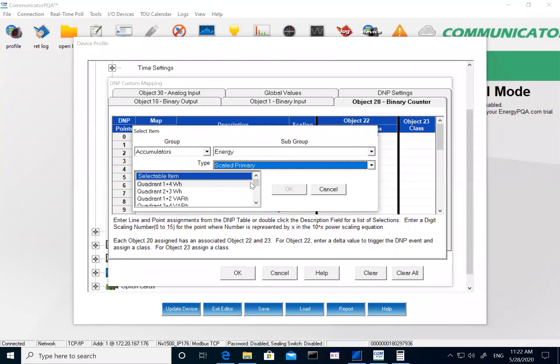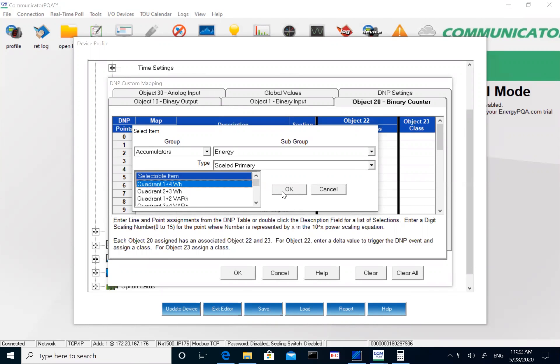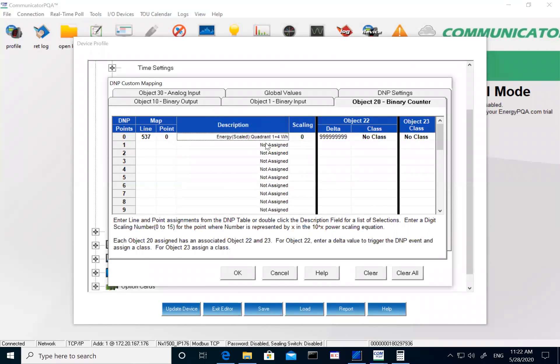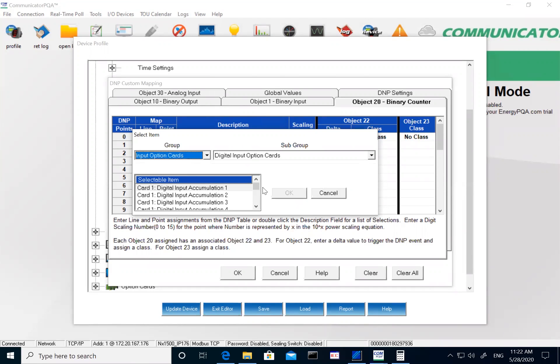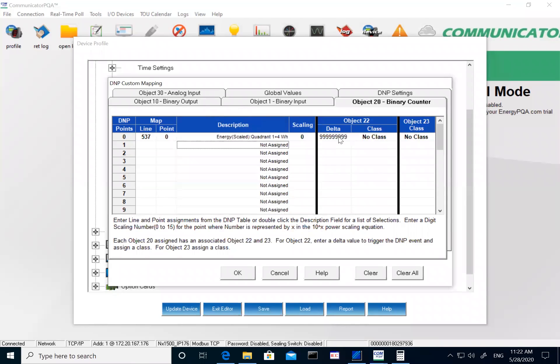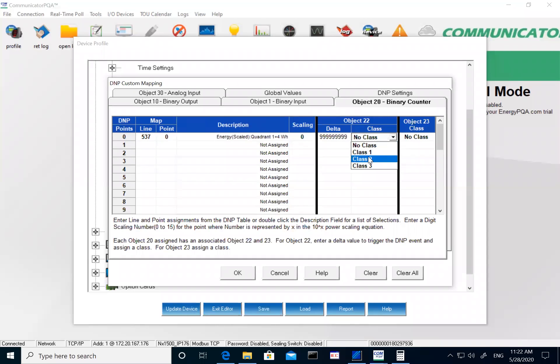On object 20 you can set up the point — for example, I want to have kWh as my DNP point. You have different options; if you have option cards, you can pull option card inputs. Similarly to what we did on the analog input, you have the ability to change the Delta — that's what triggers the alarm or events. You can configure the Delta and assign the classes for that parameter.